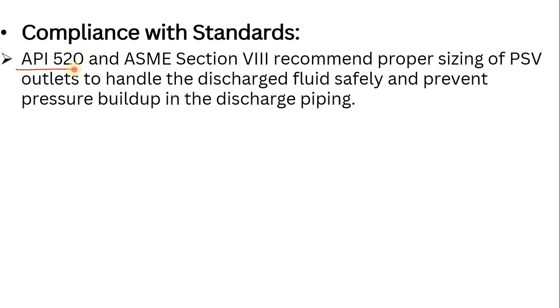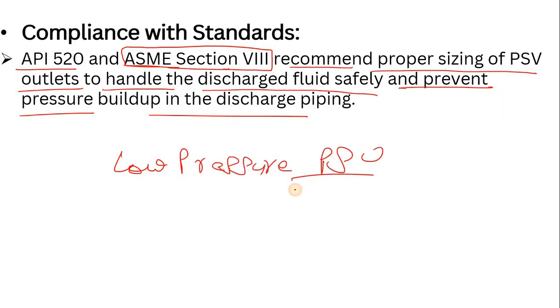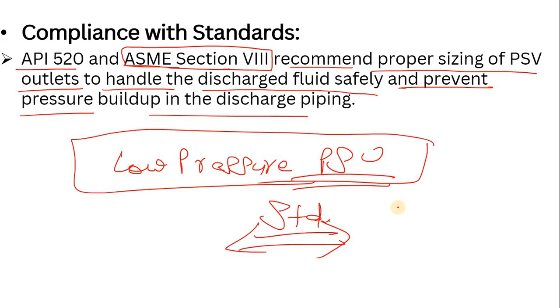Finally, compliance with standards: the standards used while sizing the PSV include API 520 and ASME Section 8. Please let me know the full form of ASME in the comments box. These standards recommend proper sizing of the PSV outlet to handle the discharge fluid safely and prevent pressure build-up in the discharge piping. For low-pressure PSVs, please let me know in the comments whether the same standards apply.